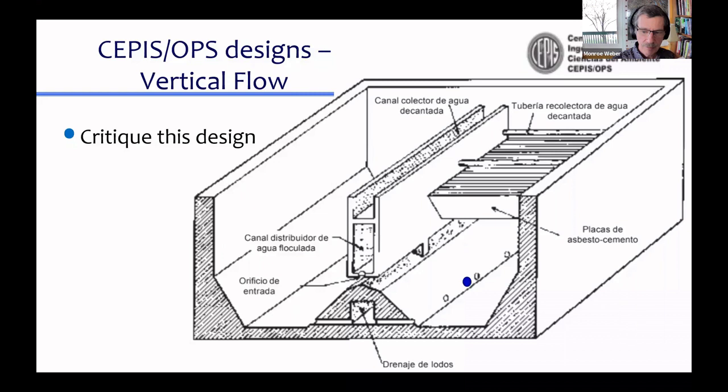Do you see that? I didn't detail that, but there's these little holes. Like here's a little hole. And that little hole is connected to this drain channel. So there's a valve at the end of that drain channel. Presumably they open up that valve and it starts sucking out of those ports. What do you think about the ability of those ports to empty the sludge that's sitting on the bottom of the sed tank?